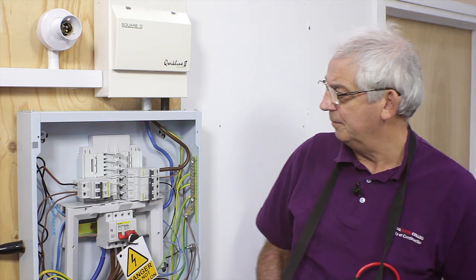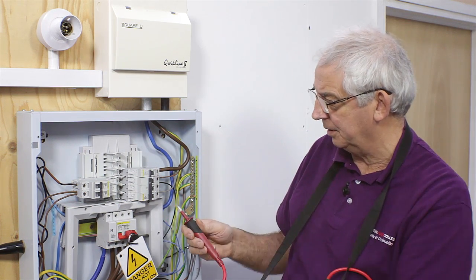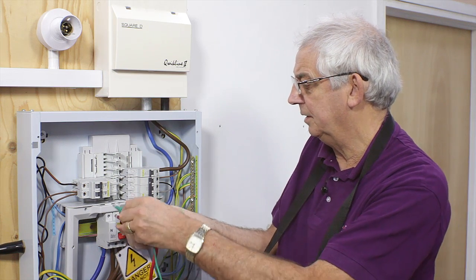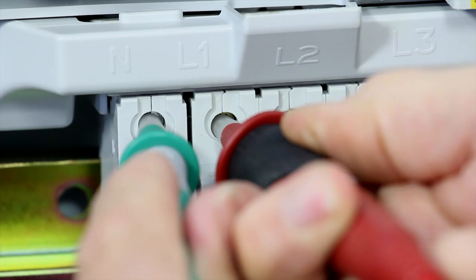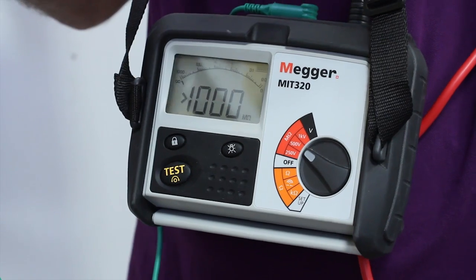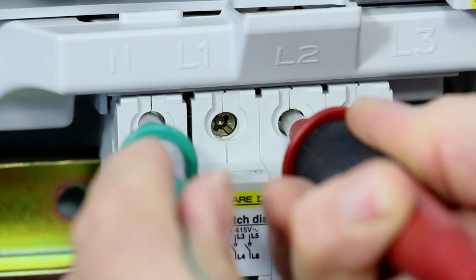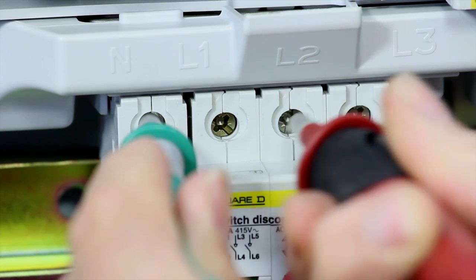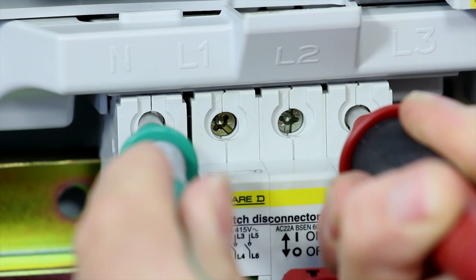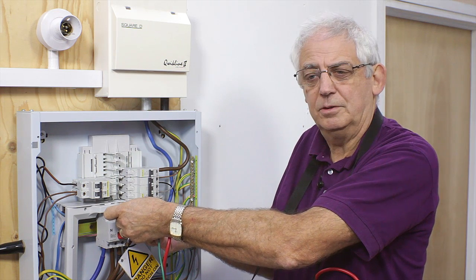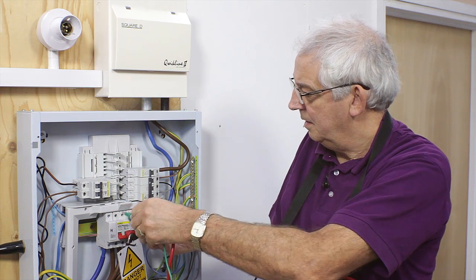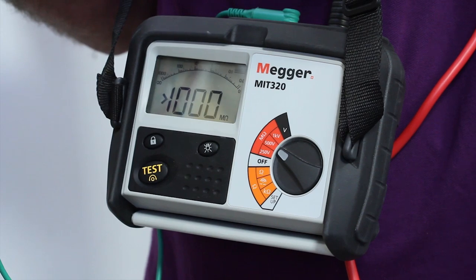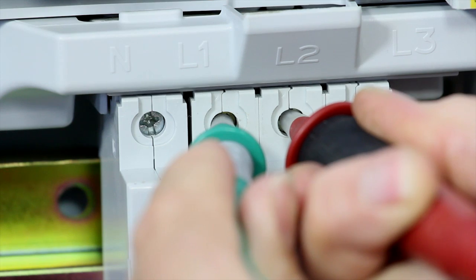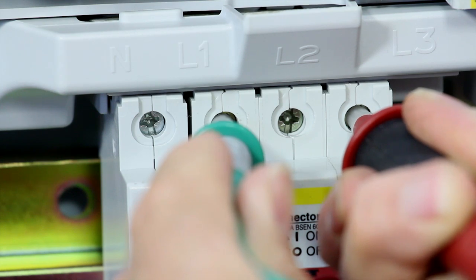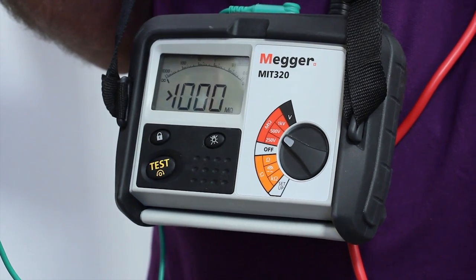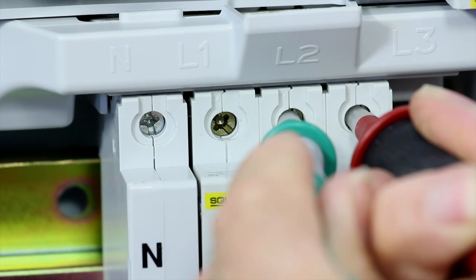So all I need to do now is go to the board and test between, first of all, line and neutral, push the button, and again, I've got a reading that's over range. L2 to neutral, again, reading over range. L3 to neutral, again, reading over range. L1 to L2, reading over range. L1 to L3, reading over range. L2 to L3, reading over range.